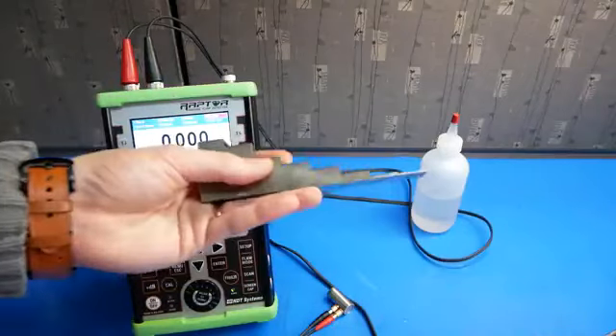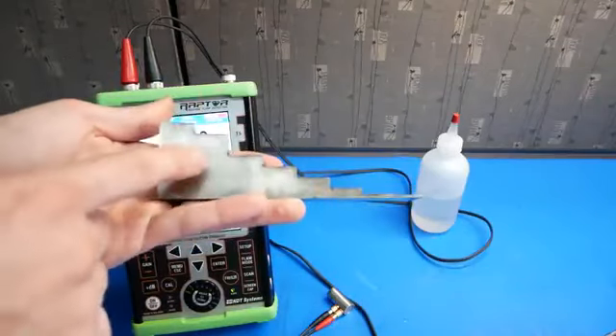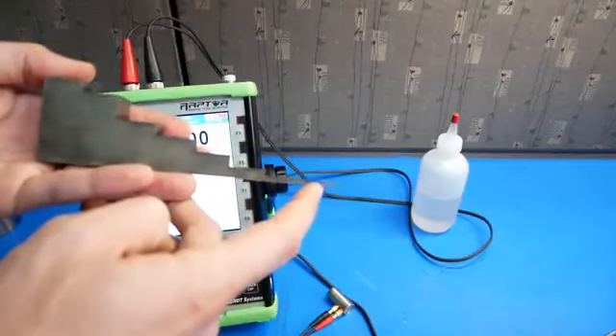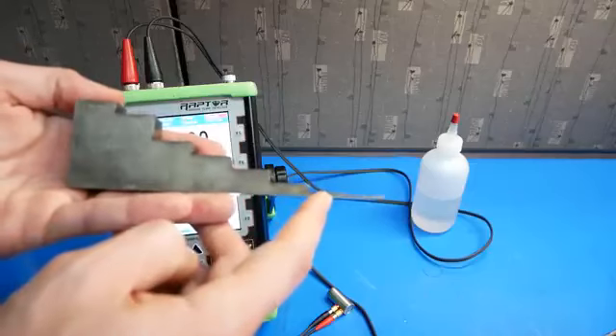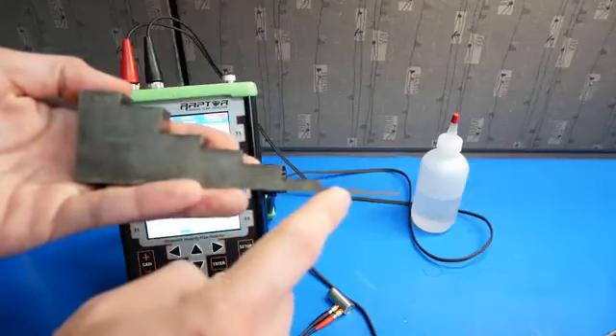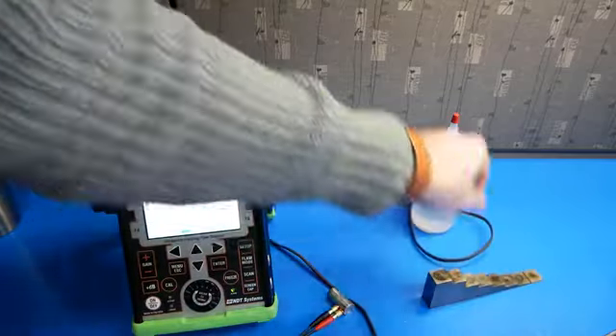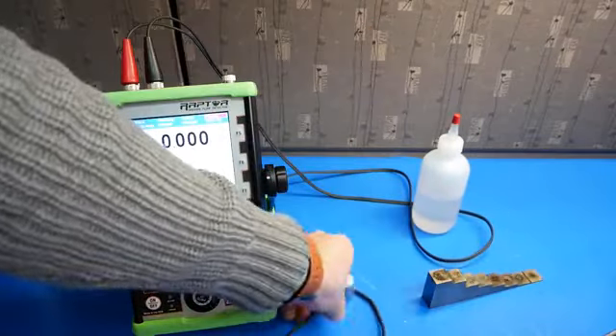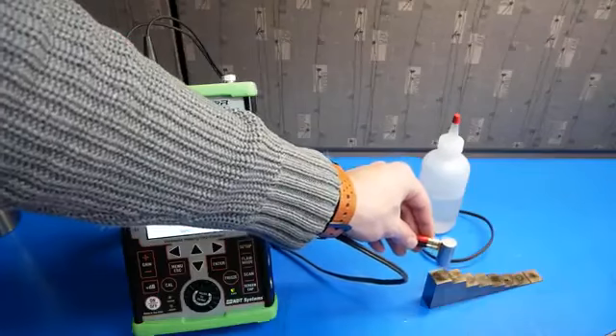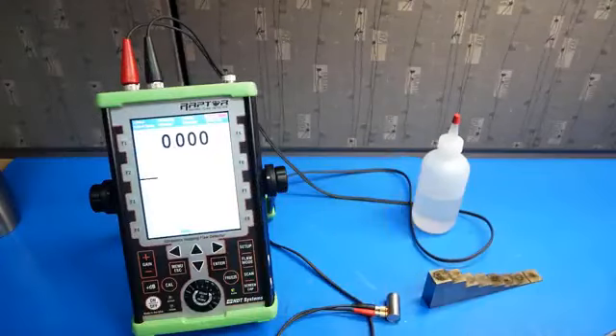We'll also need a step block with known values. This goes from 1.75 inches down to 0.062 inches. However, for our lower bound, we'll use the 0.1 inch value. We'll also need some couplant to couple the probe to the step block for accurate reading. Let's look at the menu structure of the Raptor flaw detector.